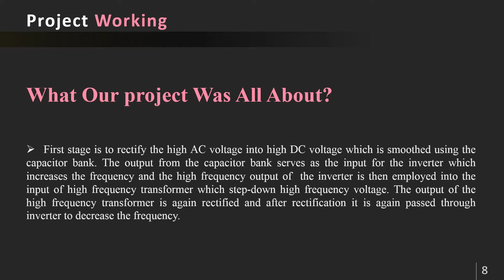Next slide is the overall detail of the solid state transformer. First stage is to rectify high AC into high DC. This is done by a high voltage rectifier. DC voltage is smoothened using a capacitor bank. The output from the capacitor bank serves as the input of the high frequency inverter, which also increases the frequency. This high frequency AC voltage is now stepped down by the high frequency transformer. The output of the high frequency transformer is again rectified and passed through an inverter to convert into 50 Hz frequency AC voltage.